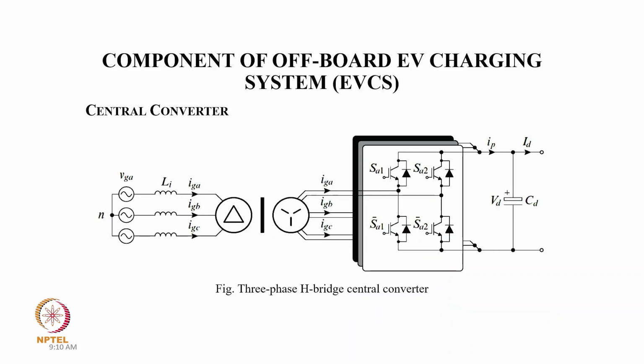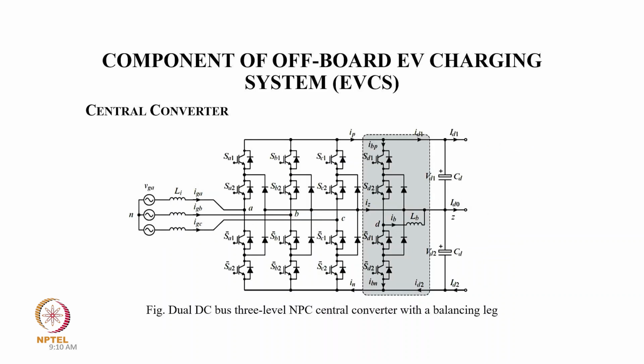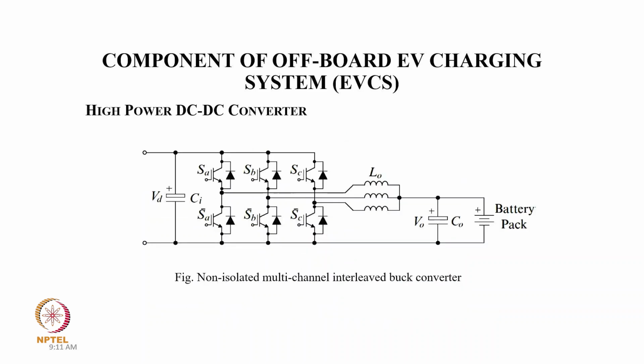Then you have another central inverter, a three-phase H-bridge, three H-bridges on three phases, which certainly has bidirectional features. The advantage of this is that you can have three single phase topologies on three phases, and you can have power factor correction on the primary side. Then this is another 3-level neutral point clamped converter for balancing the DC link voltage, and you can easily have bidirectional power flow here also. And of course, you can reduce the switching frequency as the number of levels is increased, here for 3 level. There is another high power DC-DC converter.